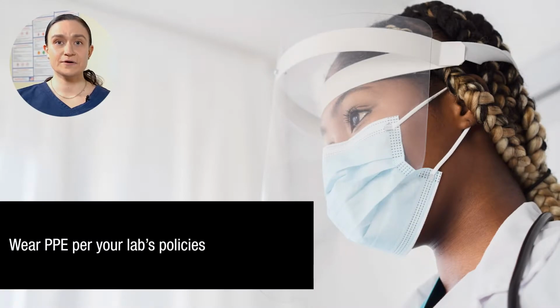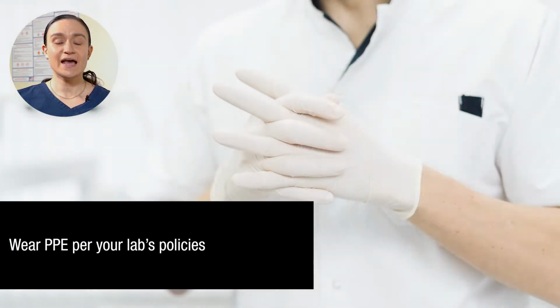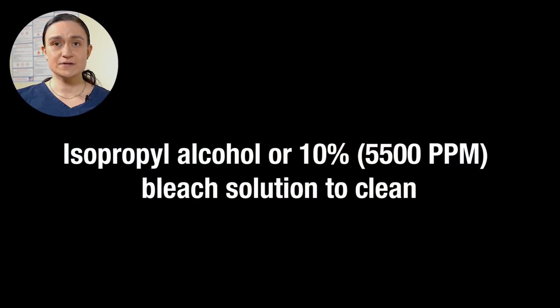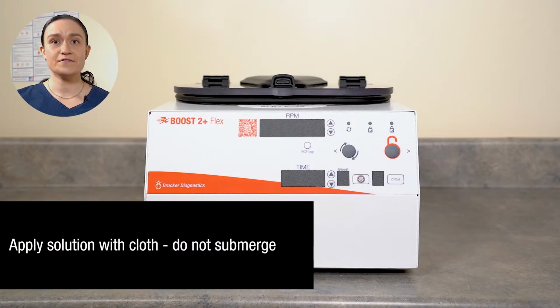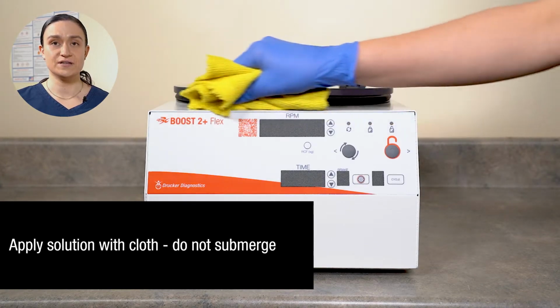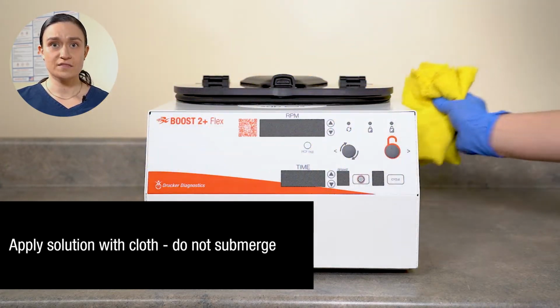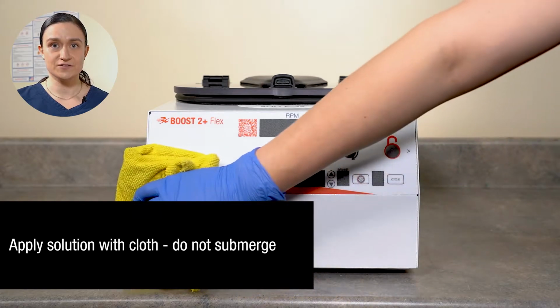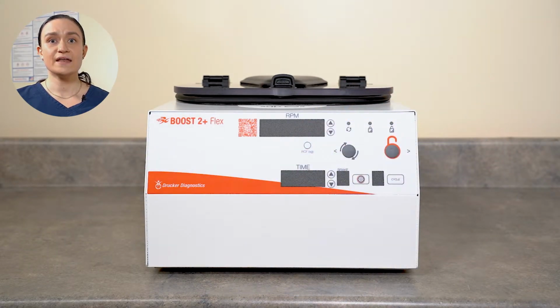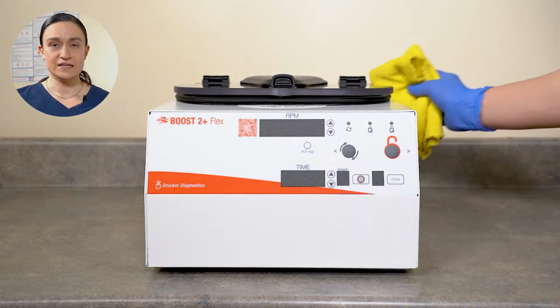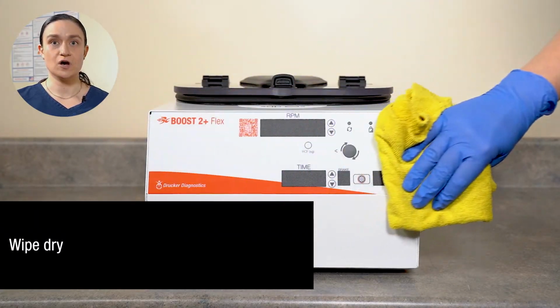Make sure you wear appropriate personal protective equipment as outlined in your lab's policies. Only isopropyl alcohol or 10% 5500 ppm bleach solution should be used to clean your Boost 2 Plus Flex. You should never submerge the centrifuge. Instead, apply your cleaning solution to a dry cloth and wipe it across the centrifuge. You should then immediately use another clean dry cloth to wipe the centrifuge off.